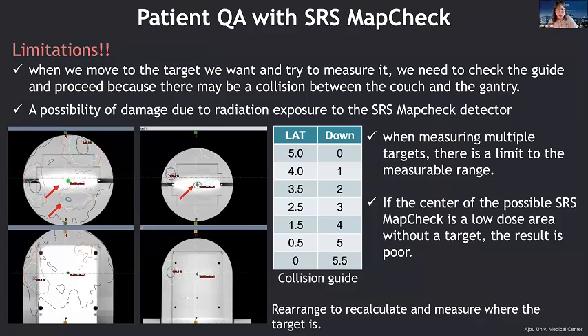So we measure with a non-coplanar angle, but when we move the targets and try to measure them, we need to check the couch angle and the process because there may be a collision between the couch and gantry, which means the phantom and gantry. If you measure with a non-coplanar angle, there is a possibility of damage to the electronic part of the SRS MapCHECK due to radiation exposure. Therefore, when measuring multiple targets, there is a limitation to the measurable range. If the center of the SRS MapCHECK is in a low dose area and without the target parts, then the accuracy of the results gets really worse from my experience.